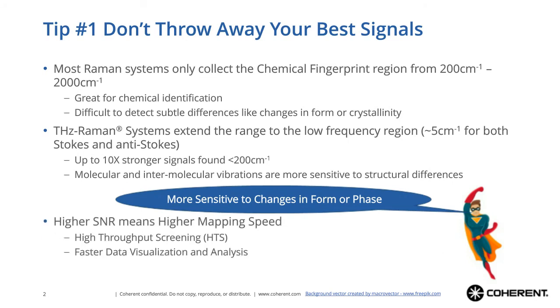The higher signal strength present in the low-frequency region means you have a much larger signal-to-noise ratio. That can enable higher mapping speeds, lower excitation power from the laser — meaning a lower chance of damaging the materials — and faster data visualization for analysis of results. This can be really crucial for applications such as high-throughput screening.